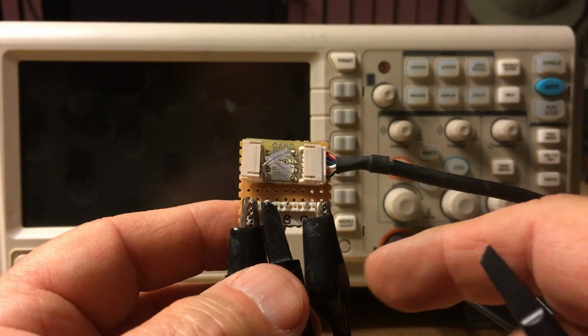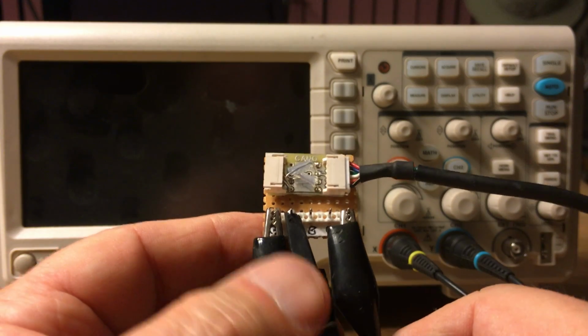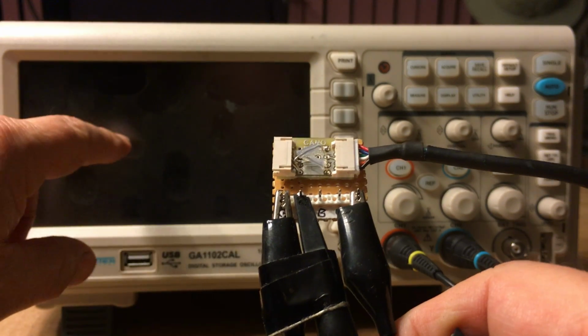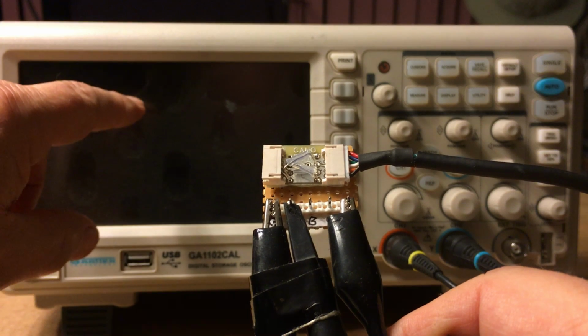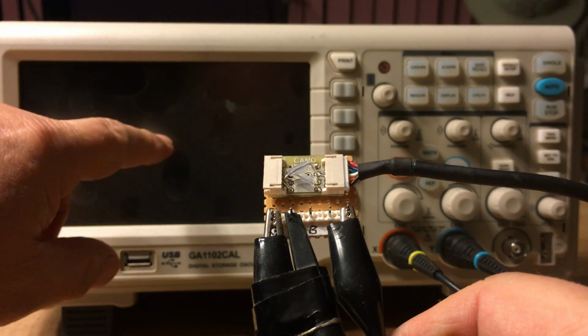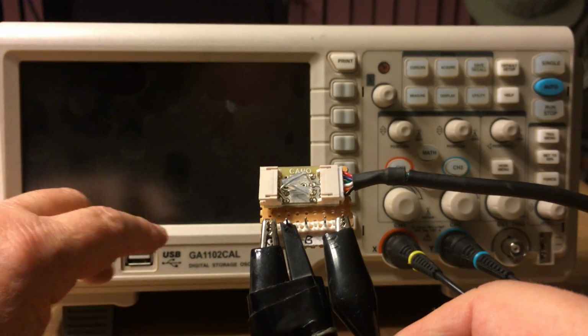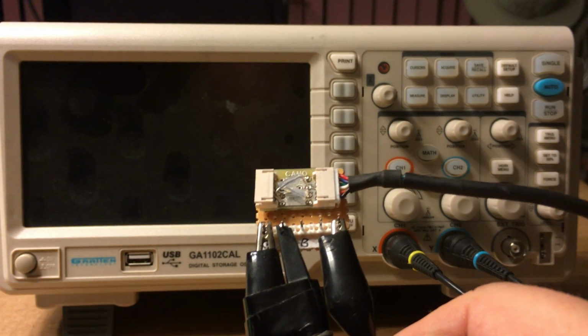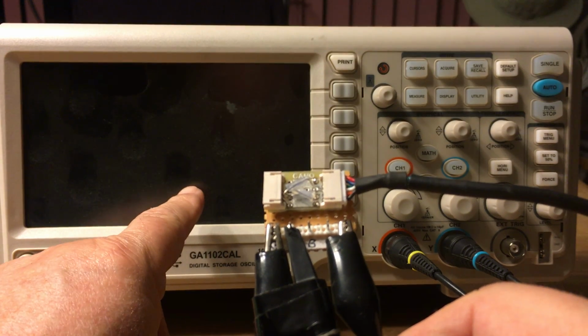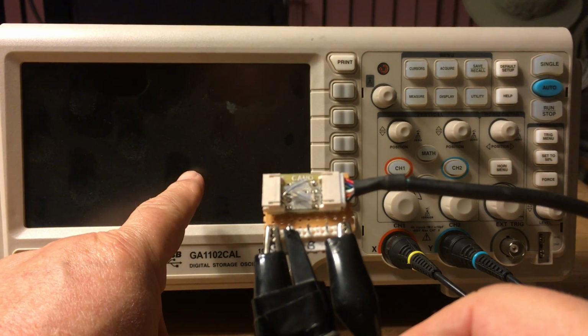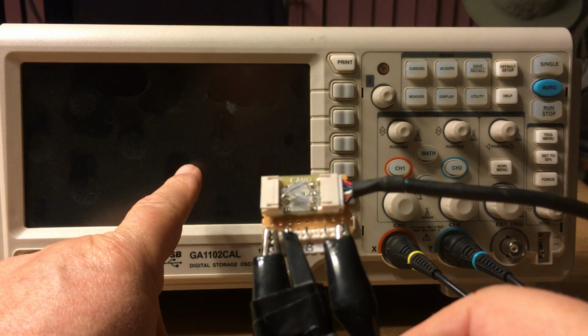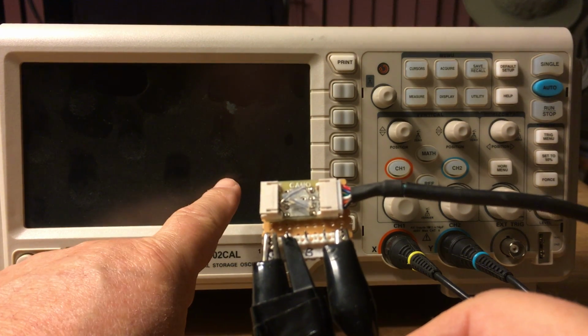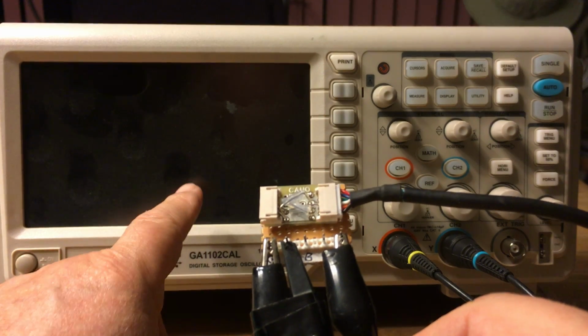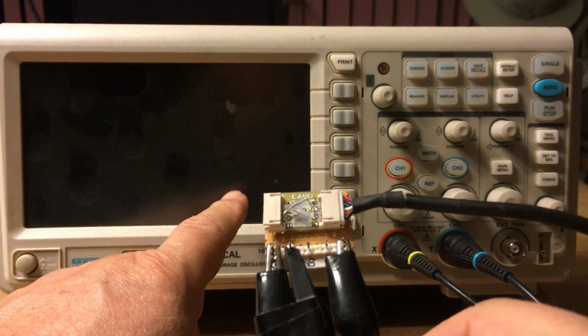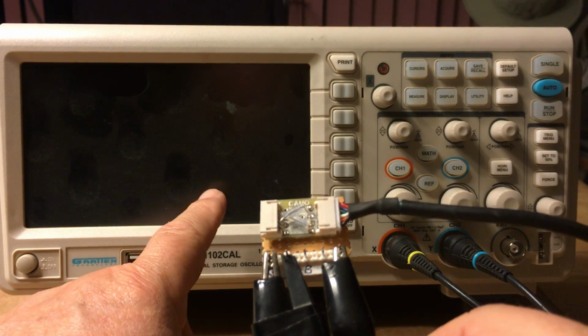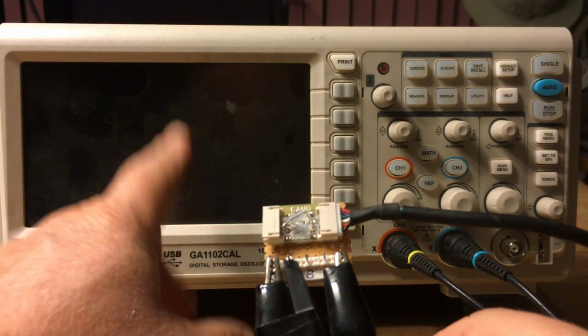So what we're really going to do here is try to read a signal on this screen from when the Hall effect sensor in the motor sends a signal back to the speed control. That'll be your trigger, or blue circuit, and then there'll be a second trace showing the speed control's power output to the motor, which should always come in time after the Hall effect sensor signals the speed control. We'll talk about that more when we actually look at the curves.